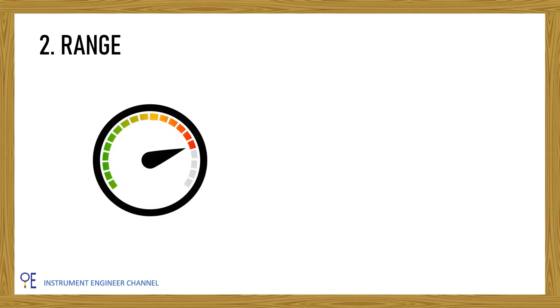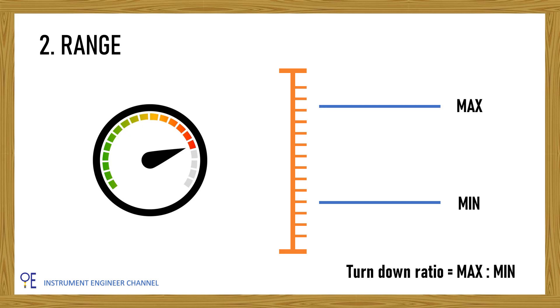The second factor is the range. Range of process variable to be measured shall be specified initially. The wide range will require instrument type which has high turndown ratio. It means some type of instrument which has low turndown ratio will not be suitable.